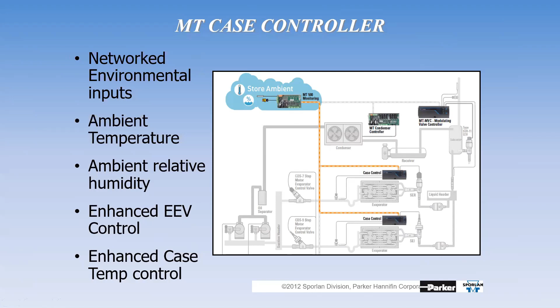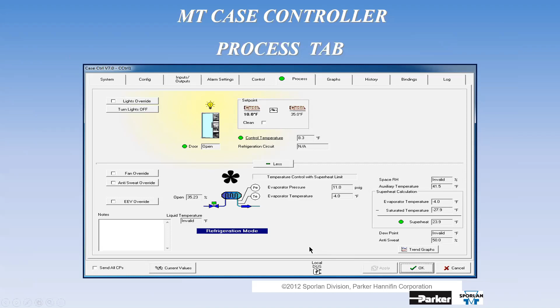This is the process tab of the case controller. 1, 2, 3, 4, 5, 6, 7, 8, 9, 10 tabs in here. Okay, so when I call this a compound node, it's not only because of the board and the pedestal board that's in there. It's because of the unbelievable amount of logic and algorithms that's built into this board. There's a ton of communication going here. So this is your process. This is going to be your landing view. It's going to tell you if it's this type of case, are the lights on or off? Is the door open and closed? How many percent open is the valve? Is the fan running? What's my temperature? What's my calculated superheat? If I want to do trend graphs, here's my button right there. I can do trend graphs right from there. What else is in here?